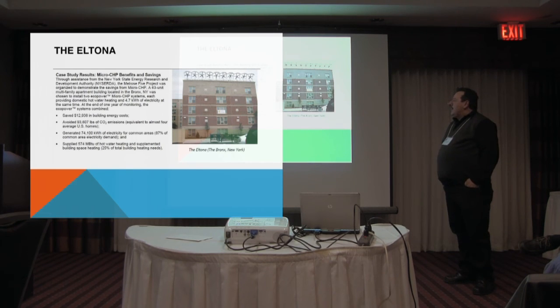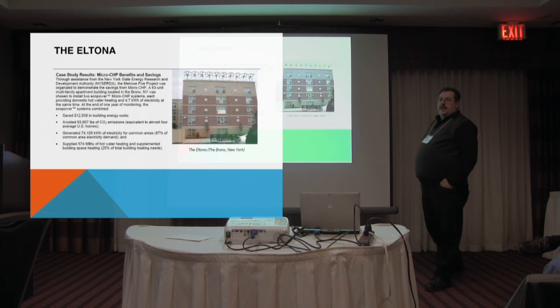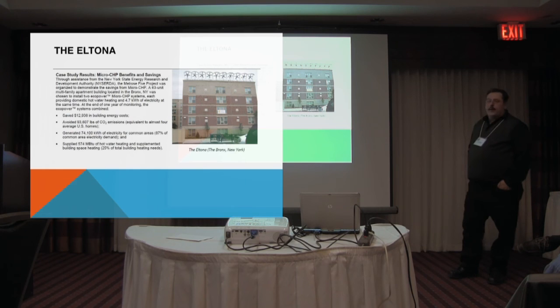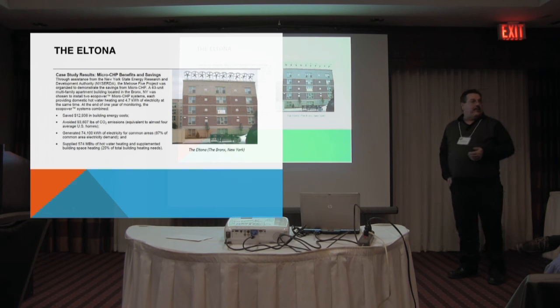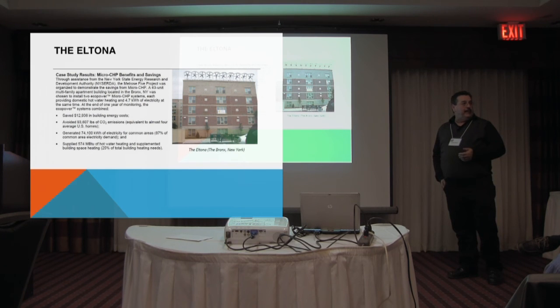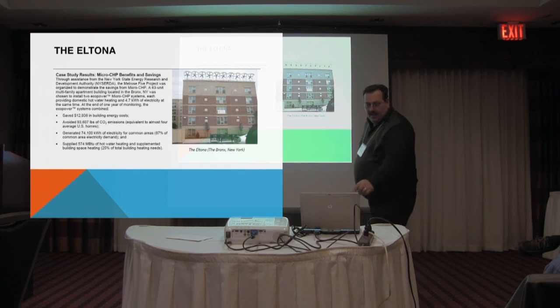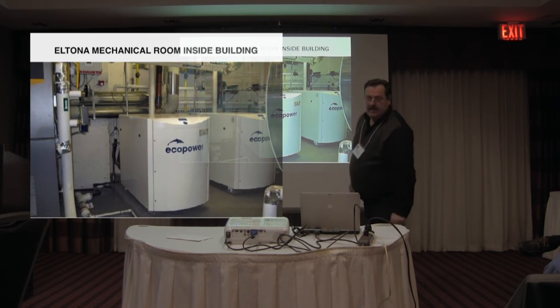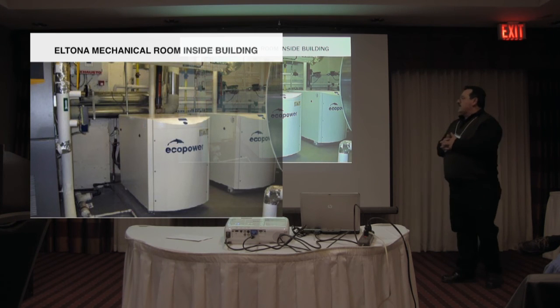So the original intent when they put these 2 units in there was to take care of the domestic water load and benefit from the electricity that was being generated to offset their common area needs. What they found is that they actually had more than enough capacity for the domestic water, but they also contributed to approximately 25% of the actual heating load for the building. So that's what the mechanical room would look like. These units are fairly compact, the size of a large boiler, if you like, but not even. Some of them are.